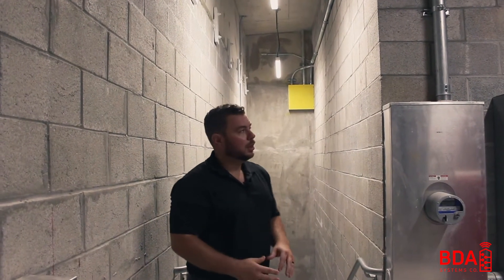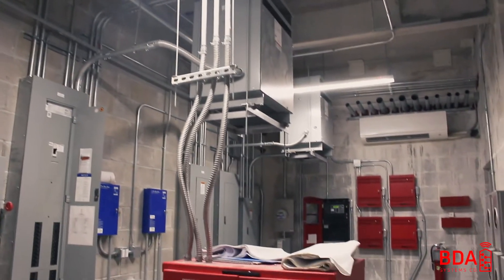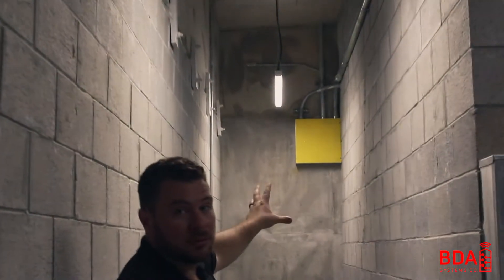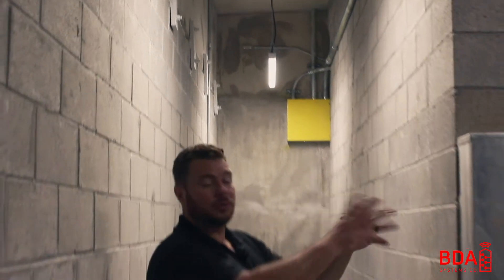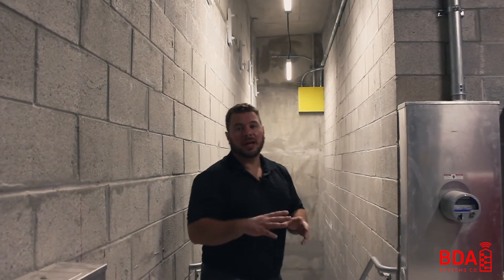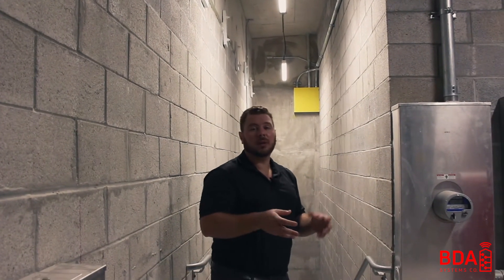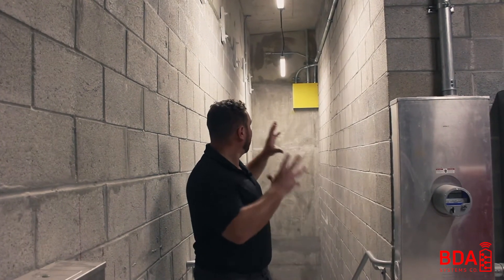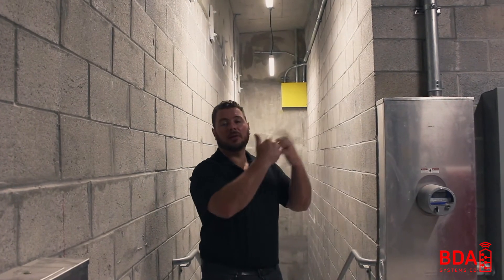Here we are on one of the first steps as we provide signal coverage to the inside of the building. On the other side of this wall is the BDA room, so we're inside another electrical room that's further removed from the BDA closet. The signal is coming down this 2-inch pipe and into that enclosure behind me. From there, we're splitting into the first floor and also continuing up. These junction boxes are really important and they have to be the right size to support the amount of splitters and couplers along with the rigid cable that we use for our systems. This main junction is a critical point — what you put at the beginning of the system will dictate how everything is down the road.